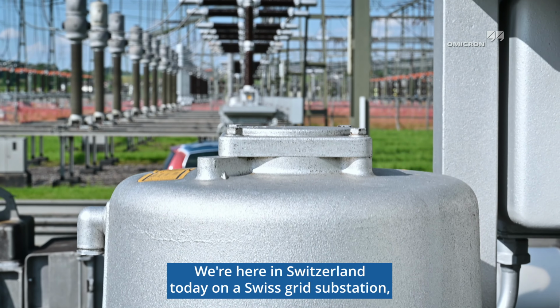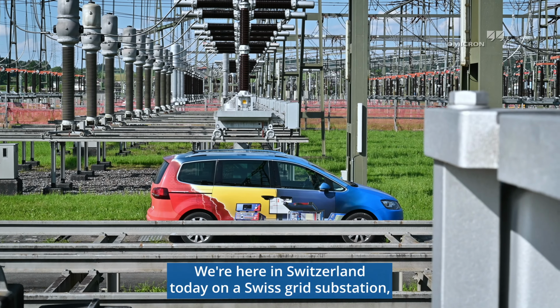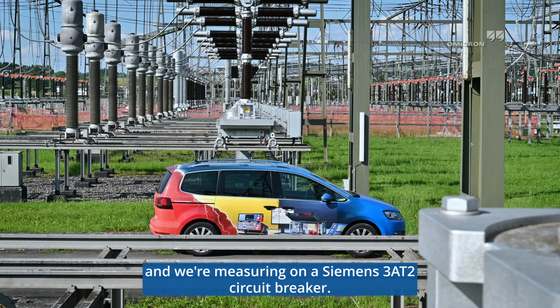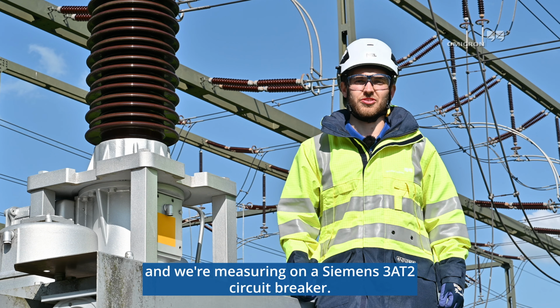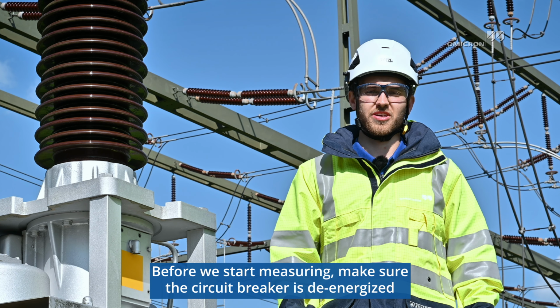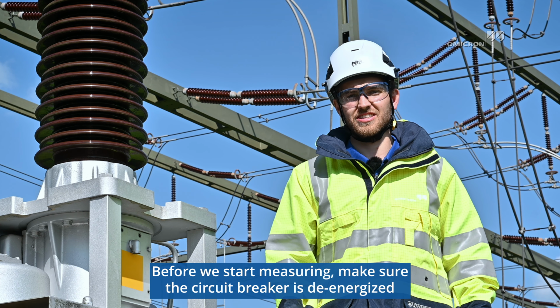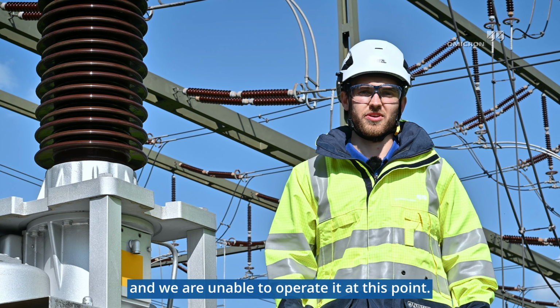We're here in Switzerland today on a Swissgrid substation, measuring on a Siemens 3AT2 circuit breaker. Before we start measuring, make sure the circuit breaker is de-energized, and we are unable to operate it at this point.